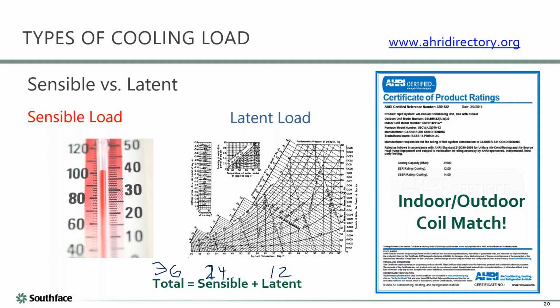So the sensible load plus the latent load makes up the total load. And there's also a term you may hear called sensible heat fraction or sensible heat ratio. In the way it's calculated, it's the sensible load divided by the total. So it's saying what percentage of the total is temperature cooling, and we know the rest is latent cooling. In my example here, it would be 2/3, or 67%, of the cooling load that is sensible, and the rest is latent.